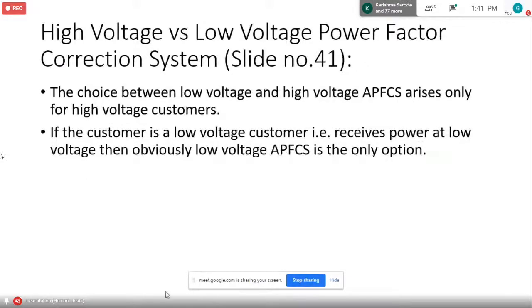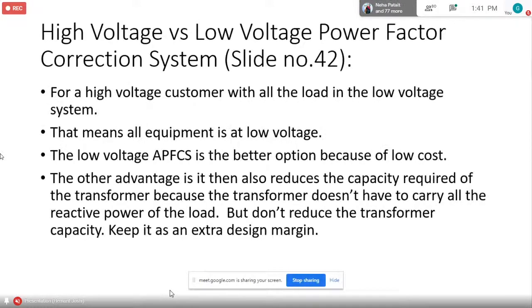All right. High voltage versus low voltage power factor correction system. The choice between low and high voltage correction system arises only for a high voltage customer. If the customer is a low voltage customer, receives power at low voltage, then obviously low voltage is the only option. For a high voltage customer with all the load in the low voltage system, that means all equipment is at low voltage, low voltage power factor correction is a better option because of low cost.